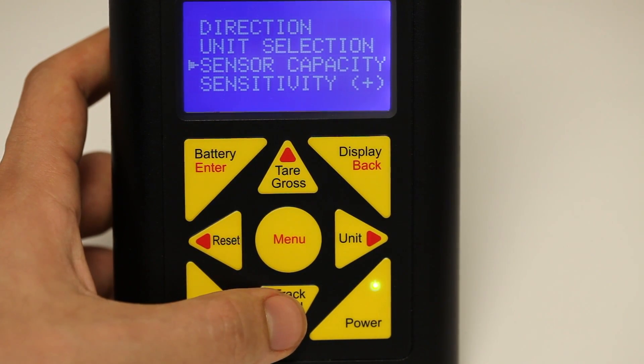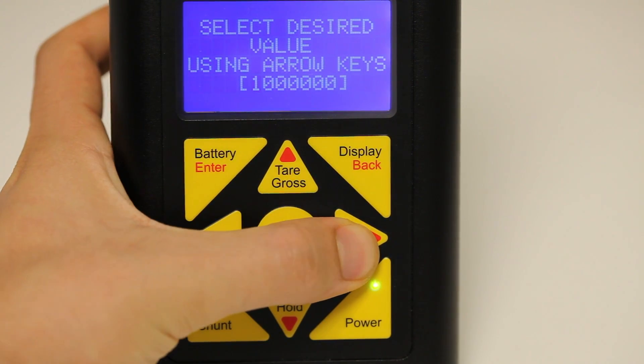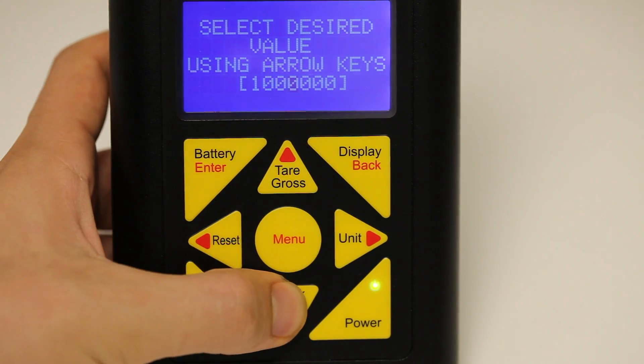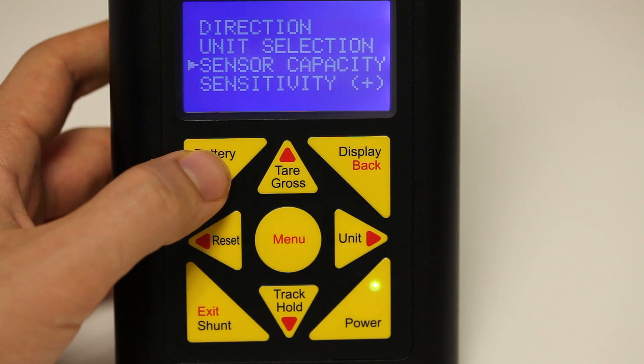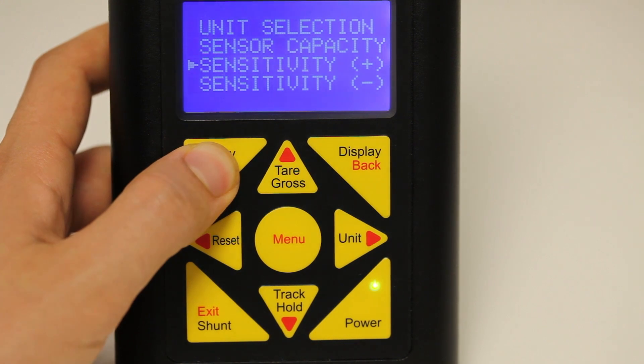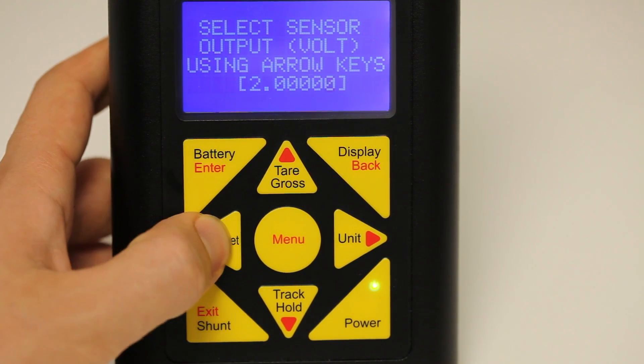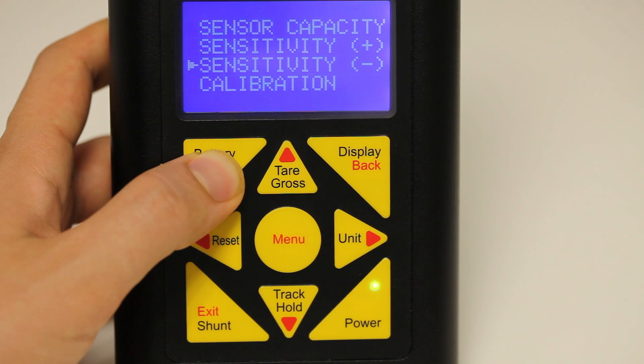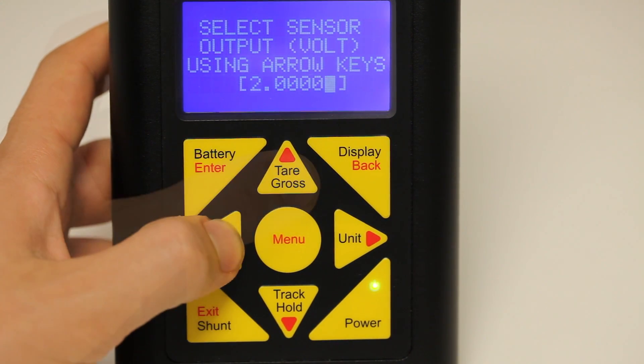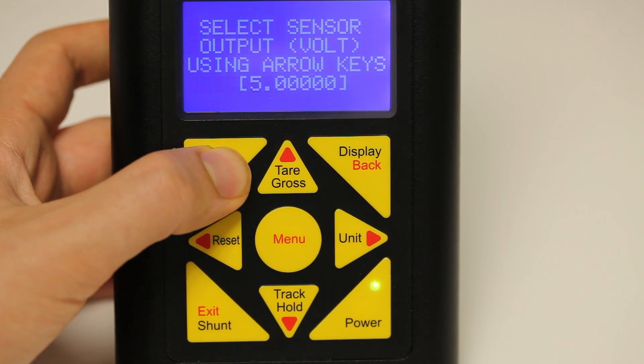Press enter to go into sensor capacity. Change the output for the appropriate capacity of your load cell. For our example, we are going to choose 100. Press enter to enter in the capacity for your load cell, and press enter to acknowledge the operation was successful. Next, press enter to go into sensitivity positive. Here, you enter in the sensitivity for your sensor for the positive direction. For our example, we will set it to 5 for 5 volts. Press enter to enter into negative sensitivity. Enter in the appropriate output for the negative direction of your load cell. For our example, we will choose 5 for 5 volts.